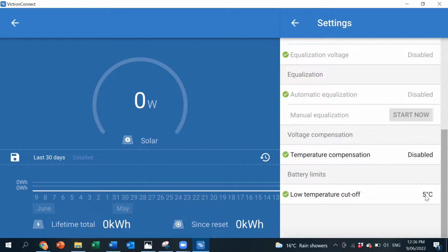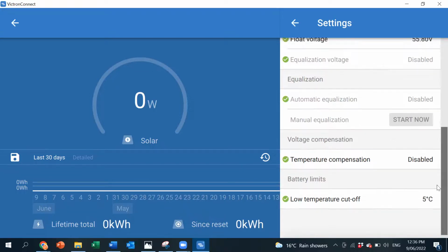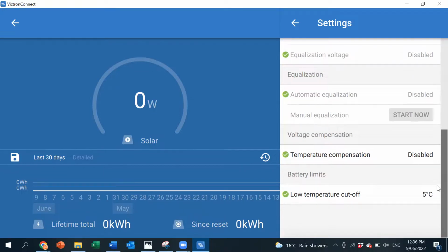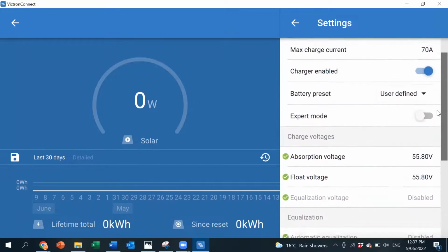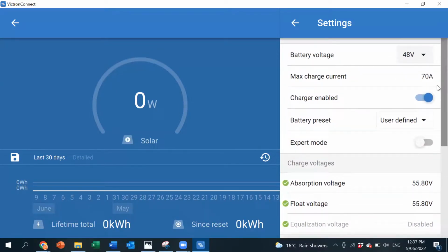Low temperature cutoff is 5 degrees as a safety. Lithium should never be charged below 0 degrees cell temperature, so that 5 degree buffer is there. And the charger is enabled, obviously, you definitely want that. Don't need expert mode, you can have a look at that if you want to, but that's done.